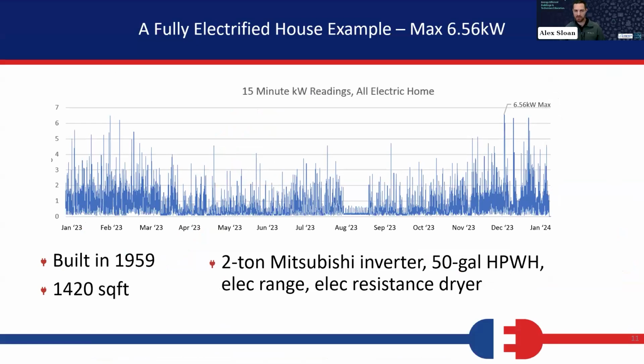Here's another example from my house in Davis, California. Over the course of a whole year, my max kW came out to 6.56 kW. The house was built in 1959 and has been fully electrified - I have a 2-ton Mitsubishi system for HVAC, a heat pump water heater, an electric range, and a resistance dryer. So we usually have lots of capacity to work with.